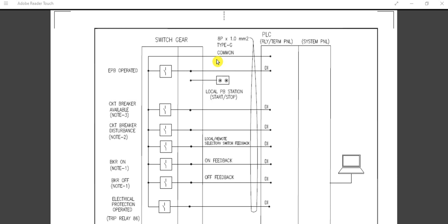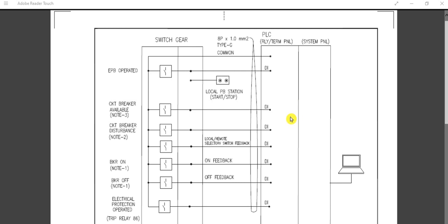First I will discuss the DI signal — DI is digital input. These are the digital input signals coming from the switchgear panels to the DCS or PLC for indication purposes only. Examples include: EPB operated (emergency push button operated), circuit breaker available, motor spring charged, and trip circuit healthy — all combinations for circuit breaker in service position.